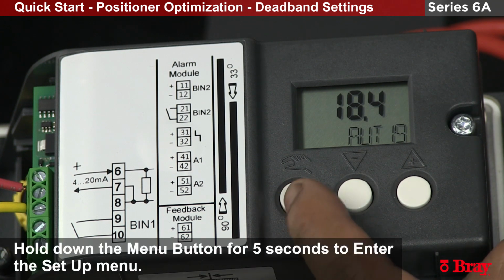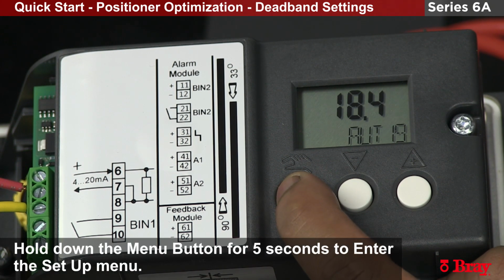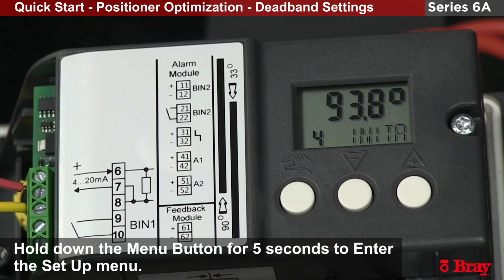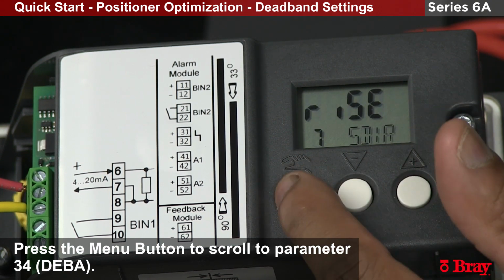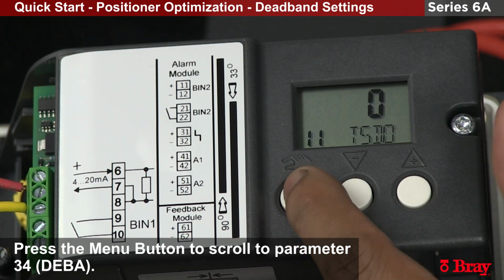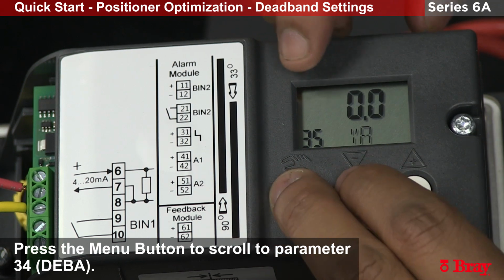To do this, we'll hold down the hand button to get into the setup menu. This will pull us out from auto and into the setup. We'll go to parameter 34, which is the deadband setting. By hitting the hand button, you can cycle through the different windows. We'll go till the window indicates 34.